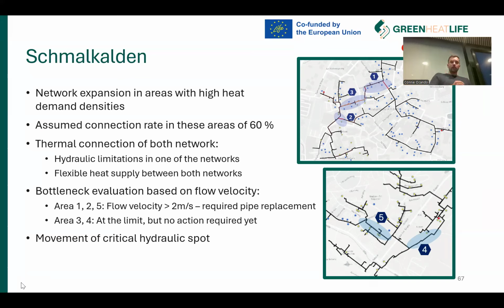So there will be some critical areas for this huge network expansion. In areas 1, 2, and 5 we reached the threshold flow velocity of 2.2 meters per second, so these pipes have to be replaced for such network expansion. However, it is quite limited, so no long network pipes need to be replaced.